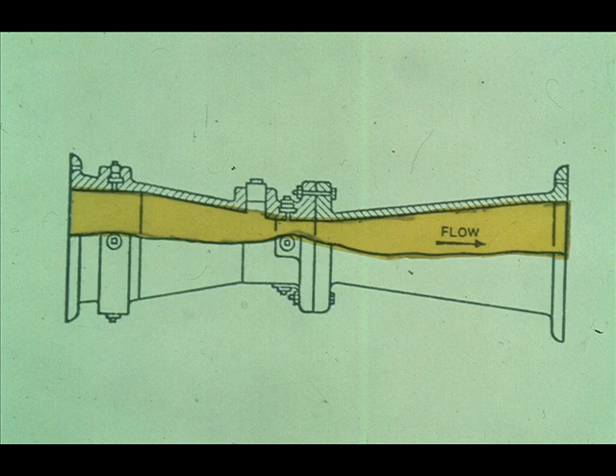Another device for measuring flow is the Venturi. Like the orifice, the Venturi causes a pressure drop which can be measured and used to calculate flow rate. The Venturi is generally more accurate than the orifice; however, it is not as widely used because it is much more expensive than an orifice plate installation.